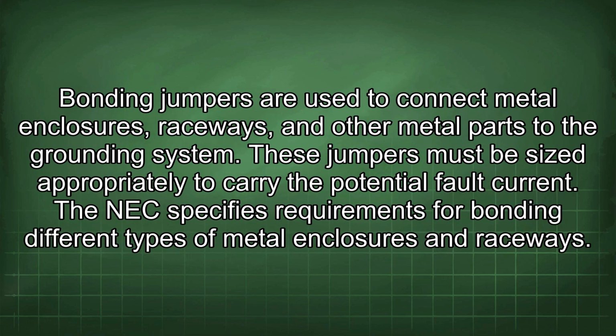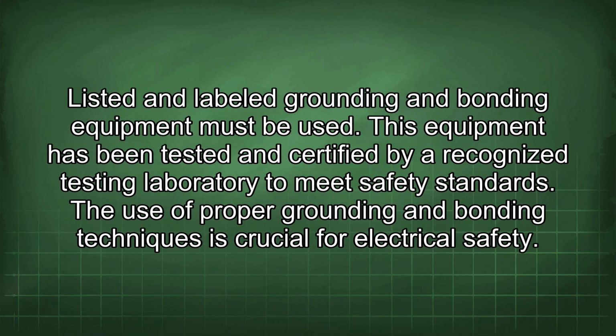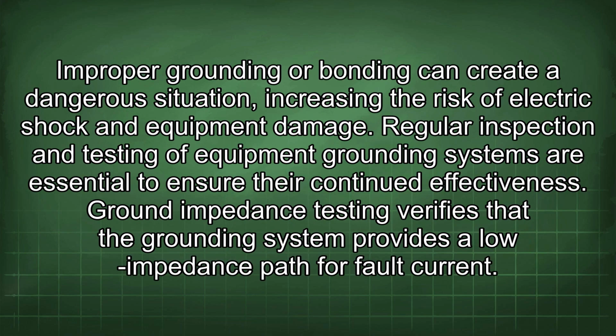Bonding jumpers are used to connect metal enclosures, raceways, and other metal parts to the grounding system. These jumpers must be sized appropriately to carry the potential fault current. The NEC specifies requirements for bonding different types of metal enclosures and raceways. Listed and labeled grounding and bonding equipment must be used. This equipment has been tested and certified by a recognized testing laboratory to meet safety standards. The use of proper grounding and bonding techniques is crucial for electrical safety. Improper grounding or bonding can create a dangerous situation, increasing the risk of electric shock and equipment damage.